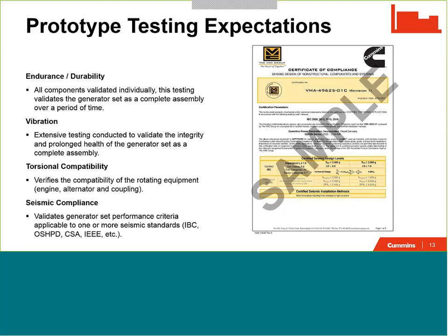It's important to ensure that the product that you're reviewing has been tested as a complete assembly. Vibration is another key piece here. There are various standards that provide recommendations or guidelines for vibration testing, but at the end of the day, an indicator of compliance from the generator set manufacturer that has stated that it has conducted vibration testing to ensure the prolonged life of the product is key. There are various standards. ISO 8528 does have some vibration guidelines. However, it is important to note that they are just guidelines, and different vendors may use different strategies to verify vibration performance.